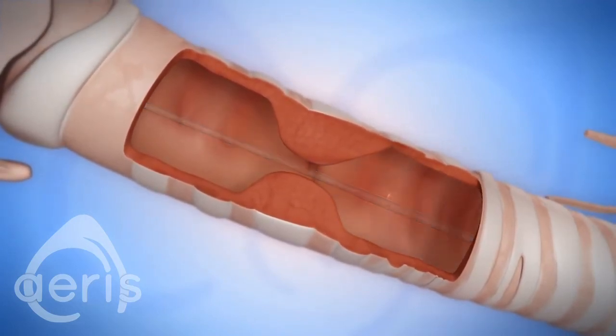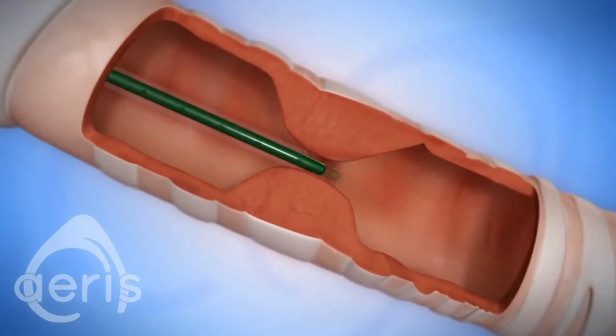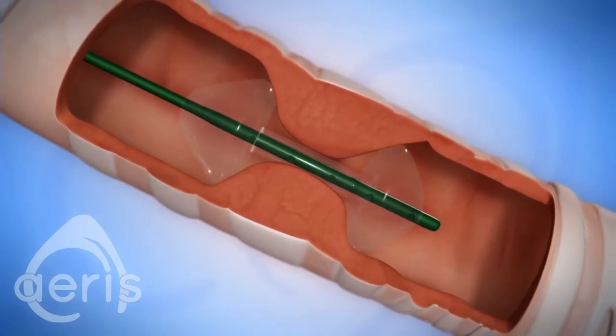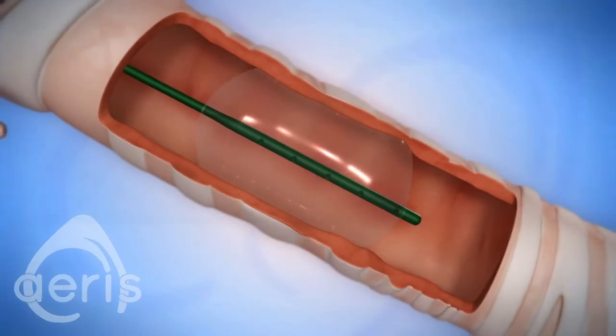The Aeris balloon addresses this issue in a safe, timely manner. Upon initial inflation, two hubs appear distally and proximally on the balloon. This locks the balloon in place over the stricture, greatly reducing the possibility of watermelon seeding.